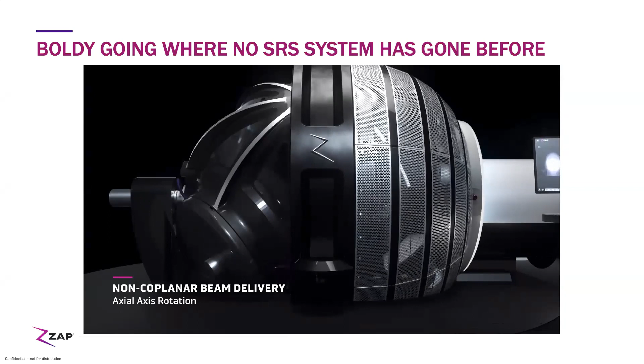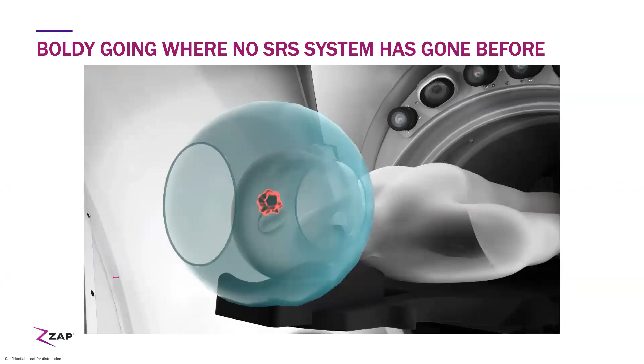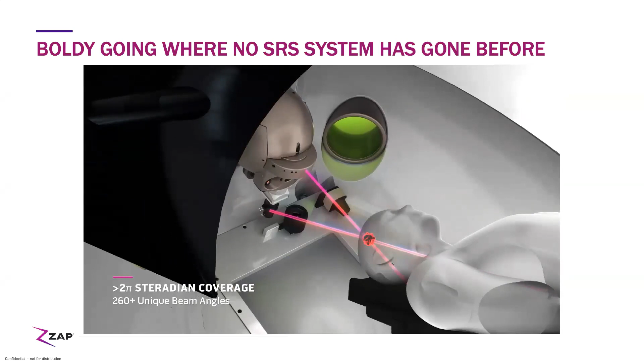So there you see the degrees of freedom on the gyroscopic mechanics, a linked gimbal within a gimbal. And this is what gives us all the degrees of crossfire. There are 260 different angles. More angles of crossfire give you better dosimetry. Boldly going where I say no radiosurgical system has gone before. And so now we're shooting using a single aperture, but we can change apertures on the fly as well. And this point of crossfire is where we get, of course, the steepest dose gradient, which is the heart of all radiosurgery.